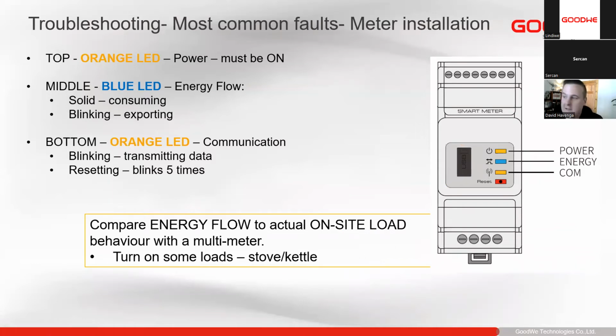So then for our smart meter, especially when we're installing this with only an on-grid inverter, our hybrids give us all the information from the smart meter. We can read a lot of information. We can even run a meter test for the smart meter on the hybrid inverters. But when it comes to the on-grid inverters, the communication with the inverters isn't the same. It's very much just some data points it's getting, and then it reacts on those data points. So the only way to make sure our installation is correct is to verify the LEDs on the smart meter.